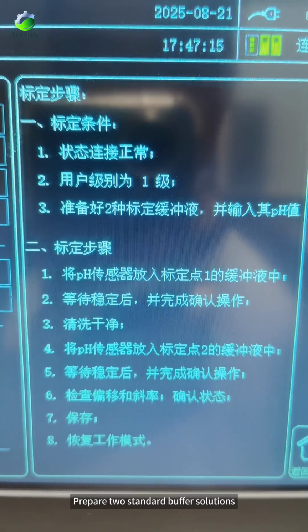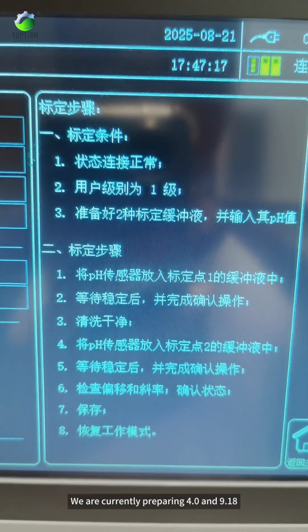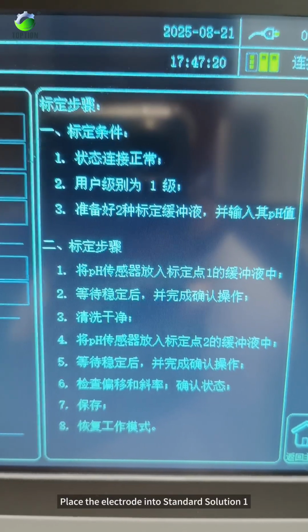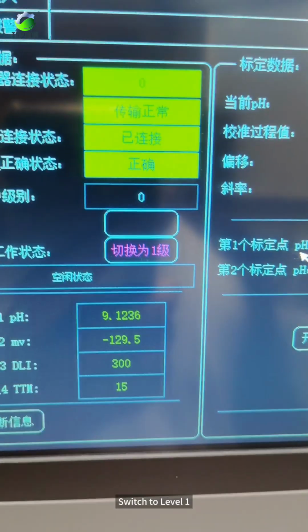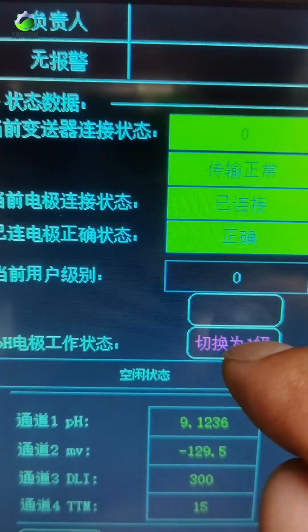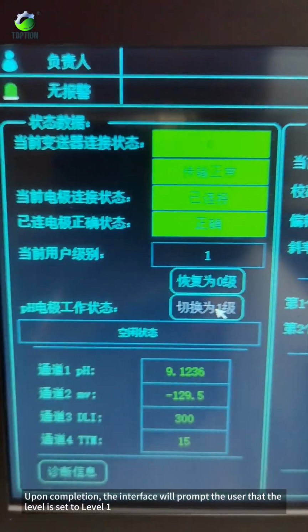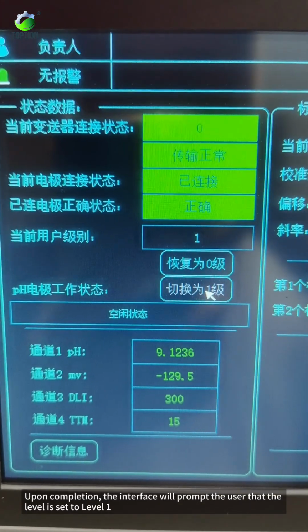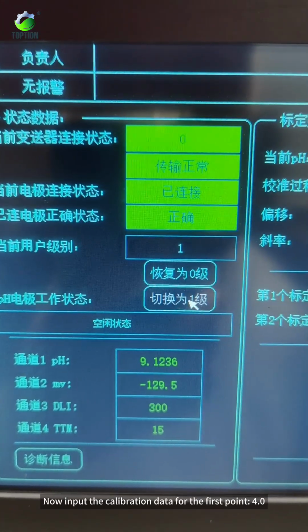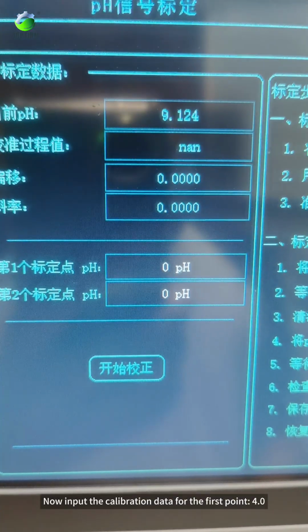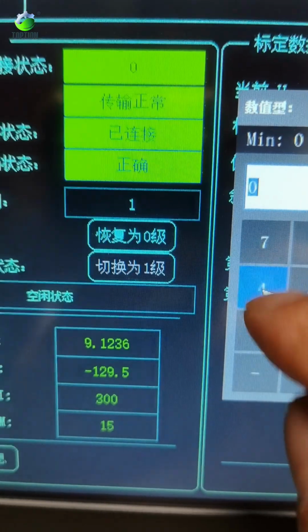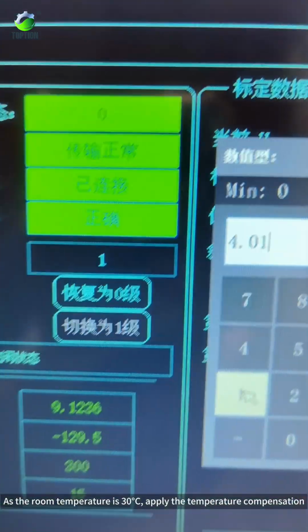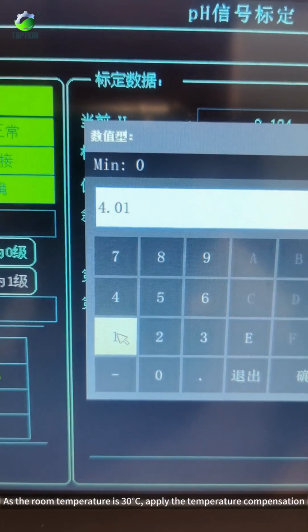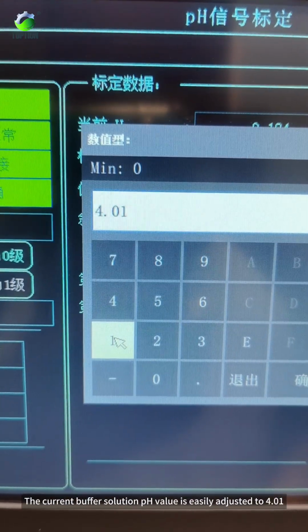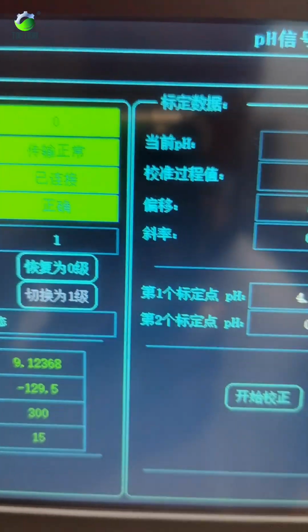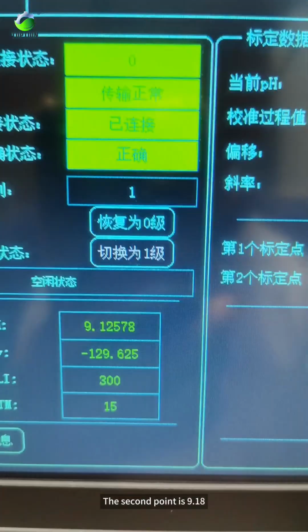Prepare 2 standard buffer solutions. We are currently preparing 4.0 and 9.18. Place the electrode into standard solution 1. Switch to level 1. Upon completion, the interface will prompt the user that the level is set to level 1. Now input the calibration data for the first point, 4.0. As the room temperature is 30 degrees Celsius, apply the temperature compensation. The current buffer solution pH value is easily adjusted to 4.01. The second point is 9.18.